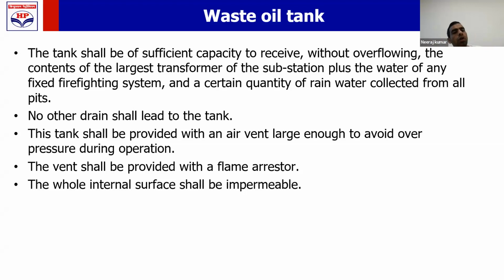Ensure that no other drain shall reach this tank. Our plant will have many drains. Those drains should not route to this tank. This tank should be dedicated solely to transformer oil.